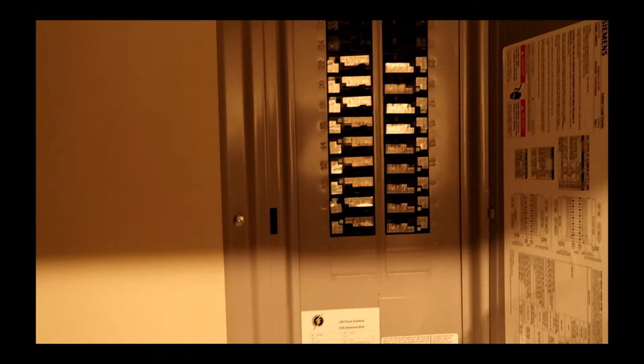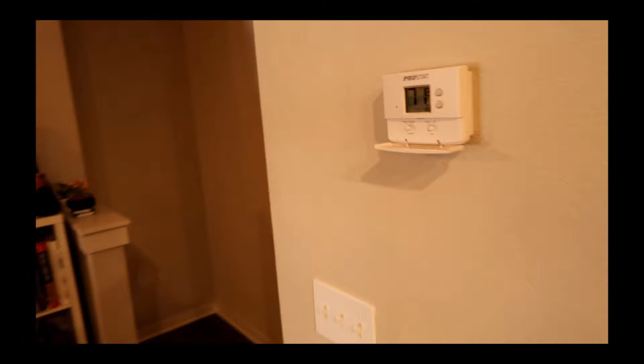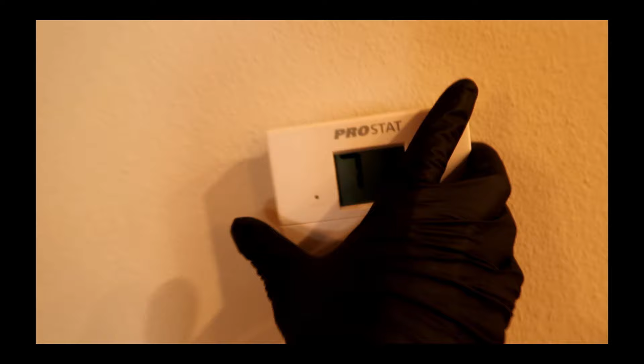Got us an old head smasher here. Let's see, turn the breaker off. Let's see if the thermostat will turn off, unless they have batteries in it. If it's got batteries in it, I'm gonna narrow it down to transformer testing. Probably don't have any low voltage coming out. Yeah, thermostat's still on, so it's probably got batteries.